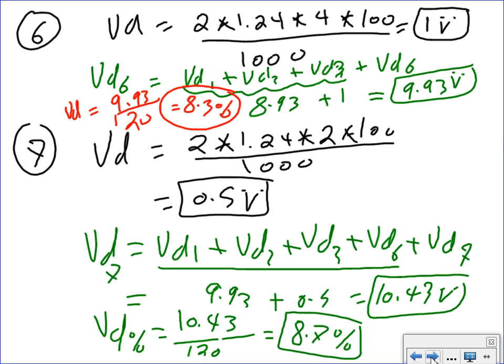DJ, my friend, before I give you a break here, this calculator is not capable of doing this type of scattered load. Electrical Calc Pro, you have to do it. You can do it, but you have to use it basically 7 times to come up with a solution. So you can't just click a couple of buttons and get the voltage drop at every single fixture right from it. This assumes that the load is lumped in one location, the source in a different one, and in between them a certain distance.